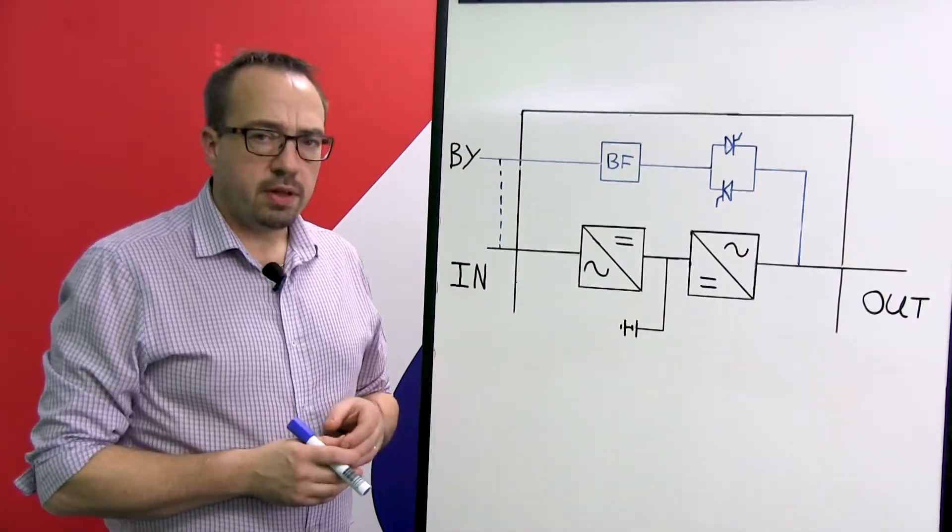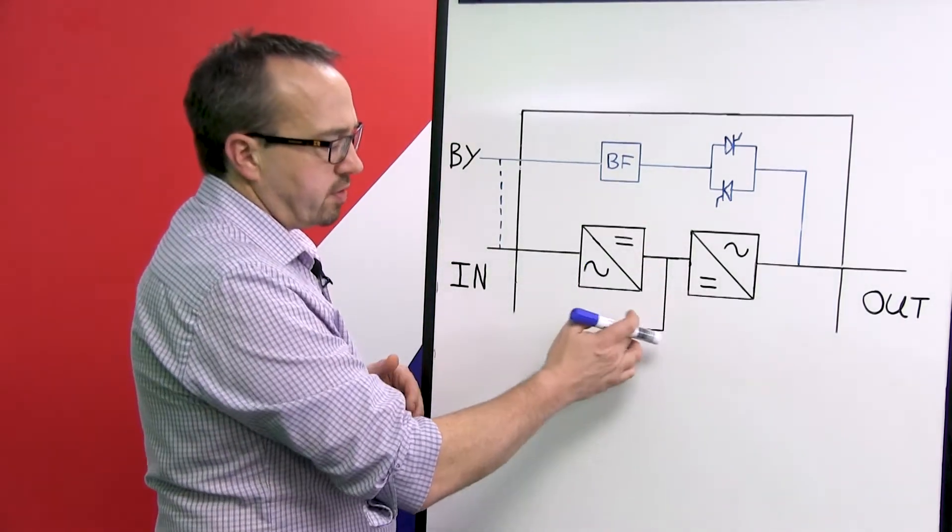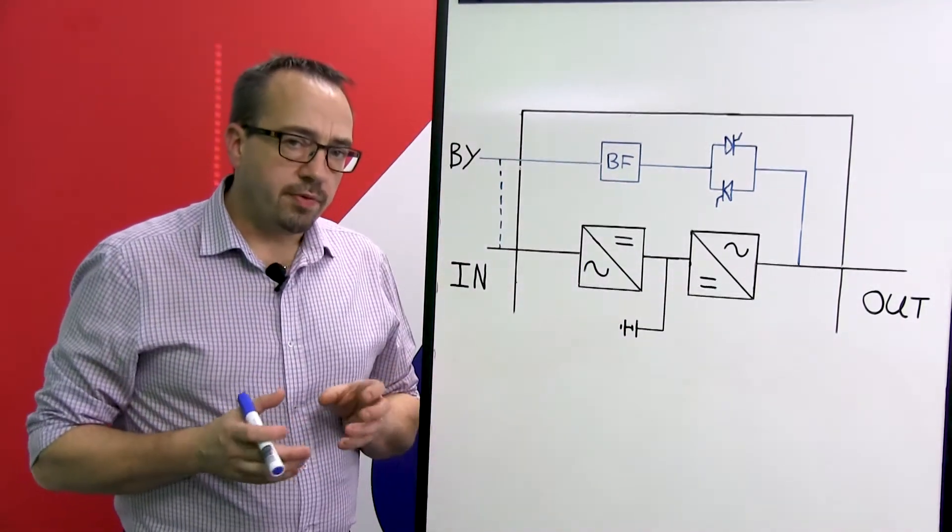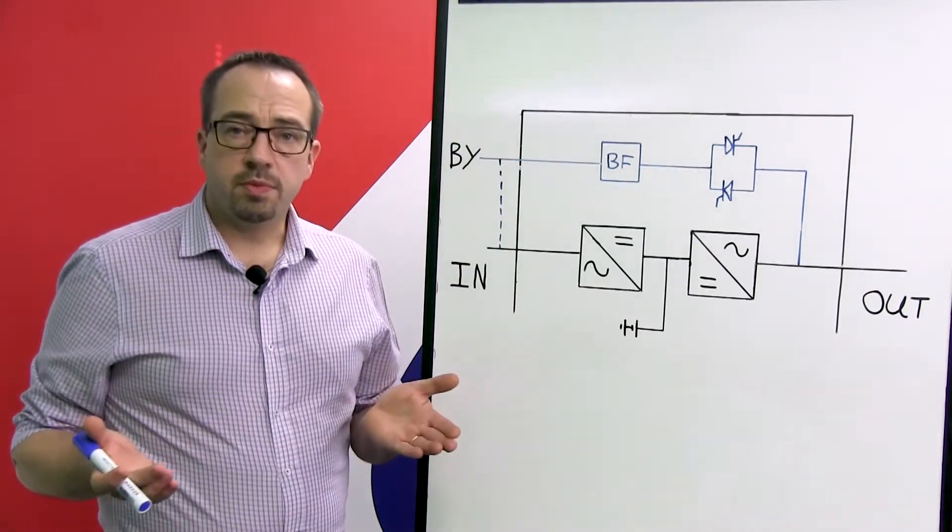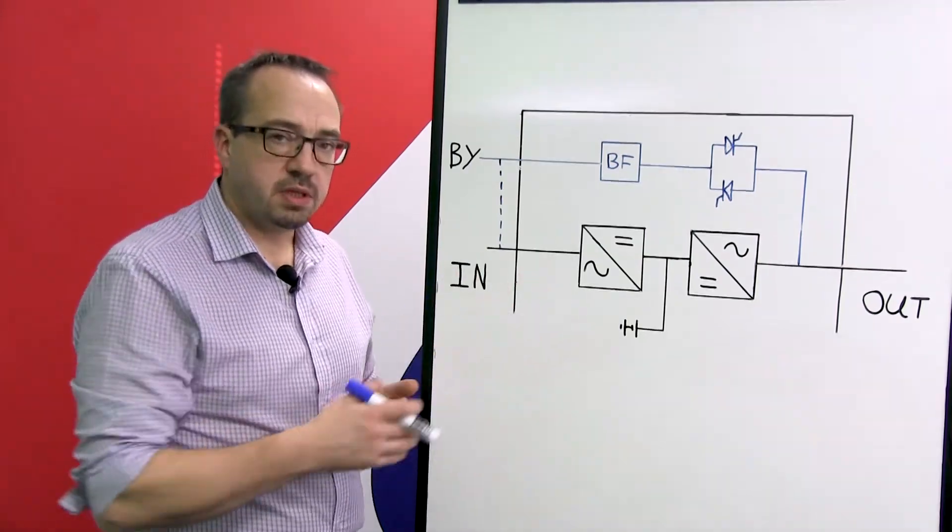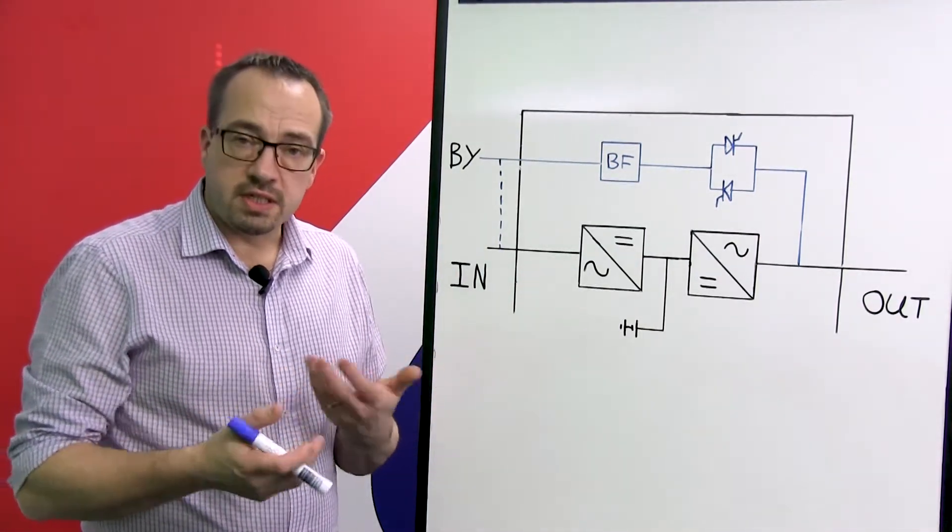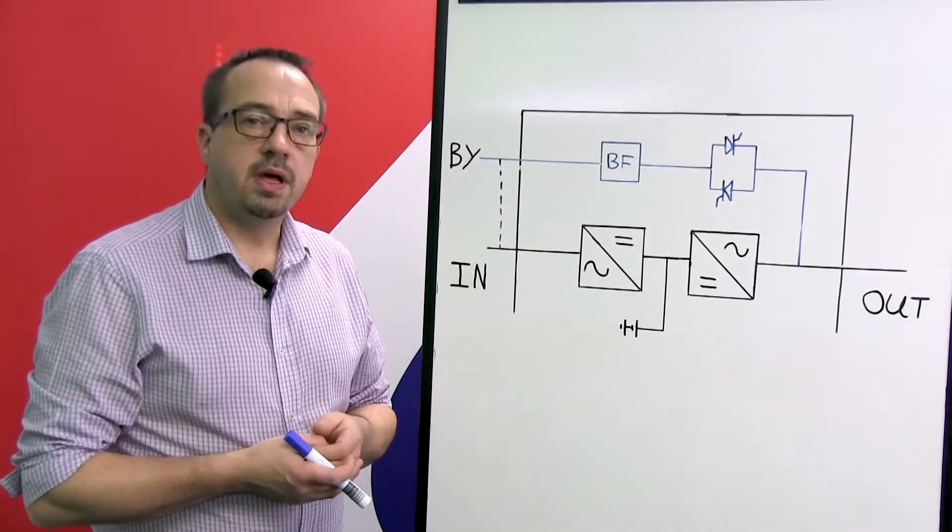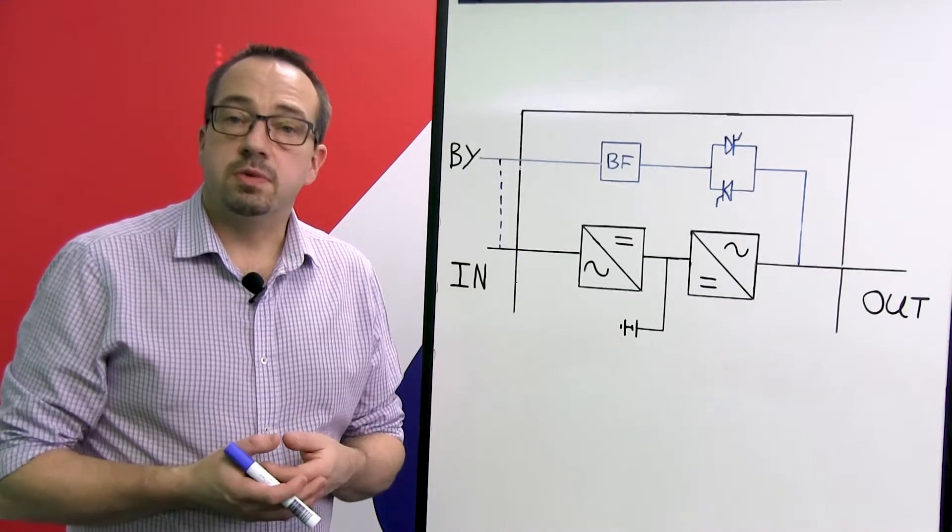Now in between the rectifier output and the inverter input are connected the batteries. Depending on the type of UPS will determine how those batteries are connected. Some systems will use a direct connection where the batteries are connected directly onto the DC bus. Some systems will use an IGBT based switching technology via a buck boost system, and some systems will utilize a thyristor based switching mechanism.